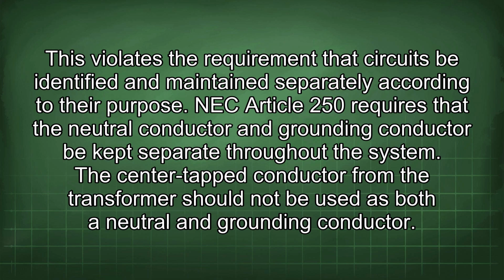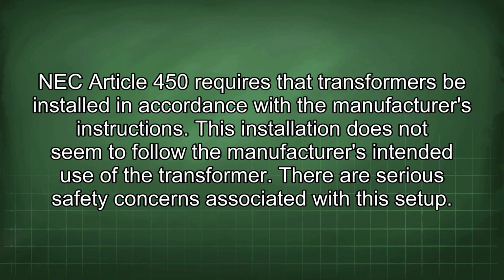NEC Article 250 requires that the neutral conductor and grounding conductor be kept separate throughout the system. The center-tapped conductor from the transformer should not be used as both a neutral and grounding conductor. NEC Article 450 requires that transformers be installed in accordance with the manufacturer's instructions. This installation does not seem to follow the manufacturer's intended use of the transformer. There are serious safety concerns associated with this setup.